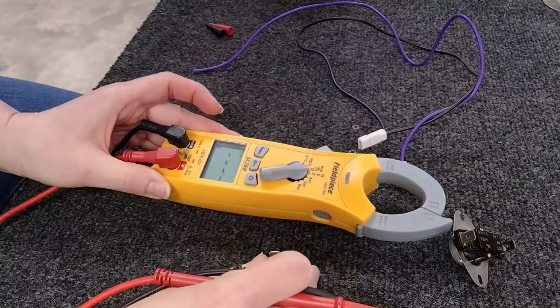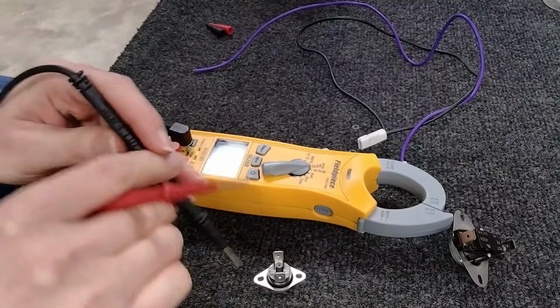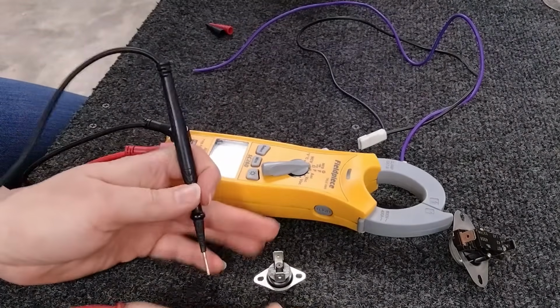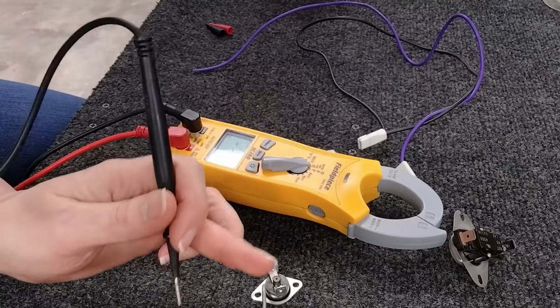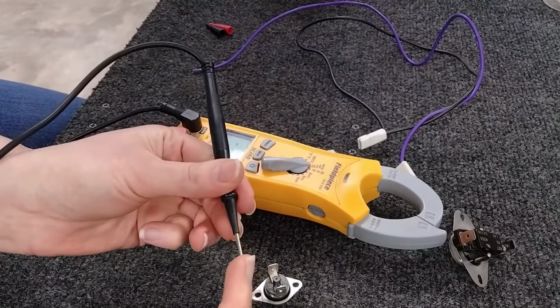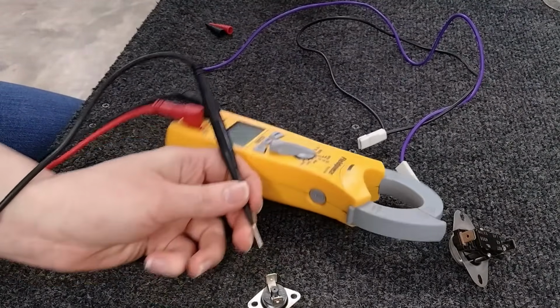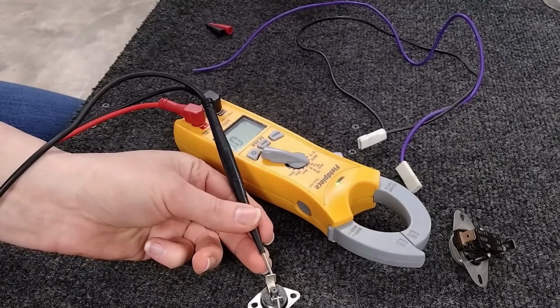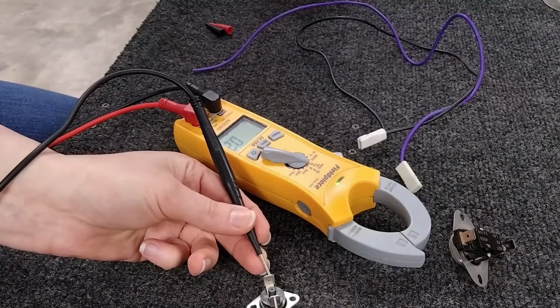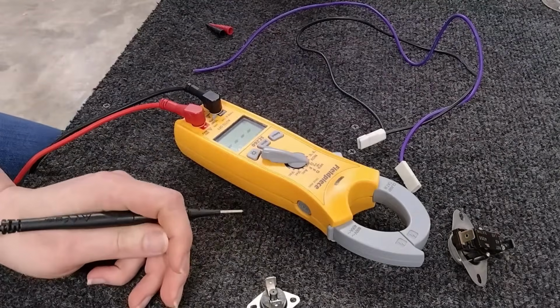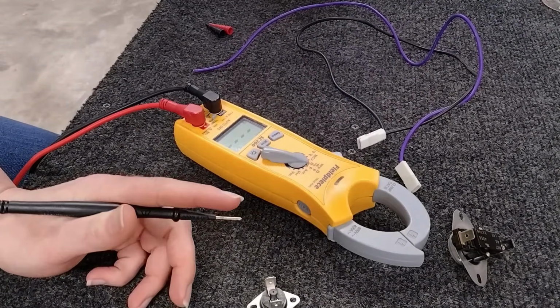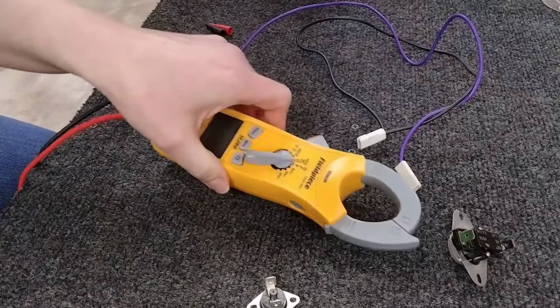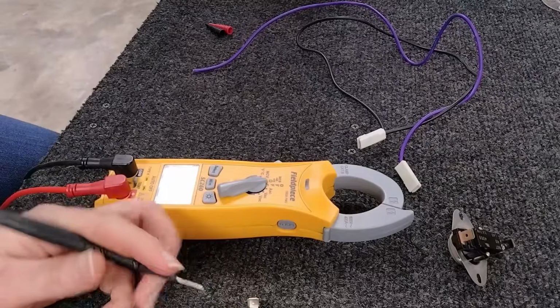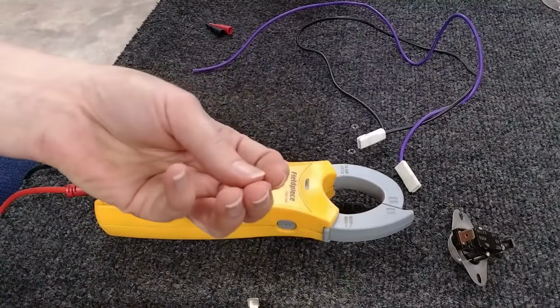We're going to put our leads on each side of these, and when you're checking with leads, try to get these edges to get a good reading. So that beep, that's a good thing. And we're reading 0.2, which is basically little to no resistance. That's great. And anything under 1 is good. Some of the older ones might read a little higher, but a 0.3, 0.4, totally fine.